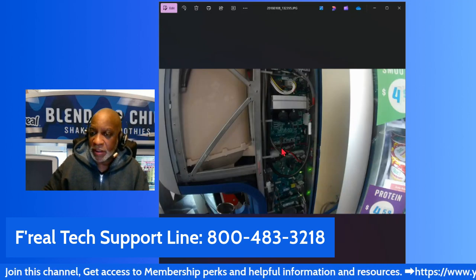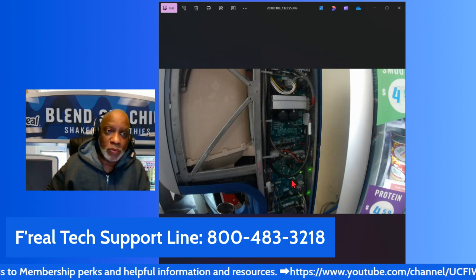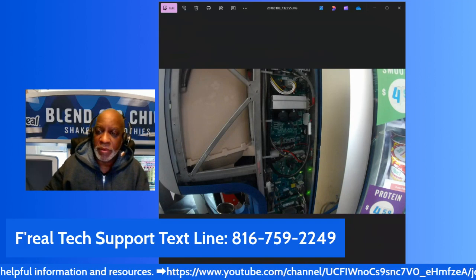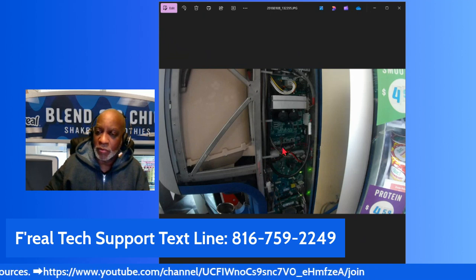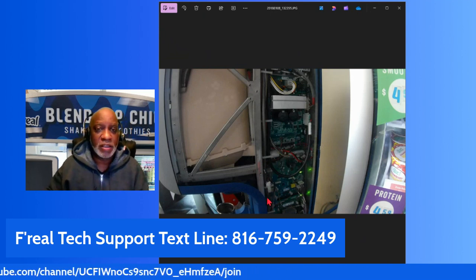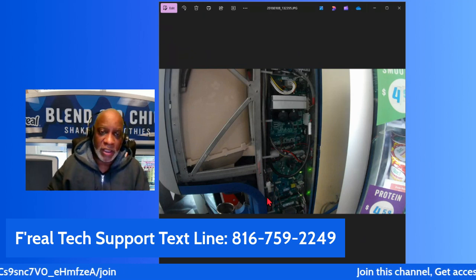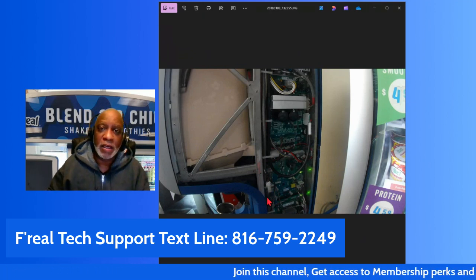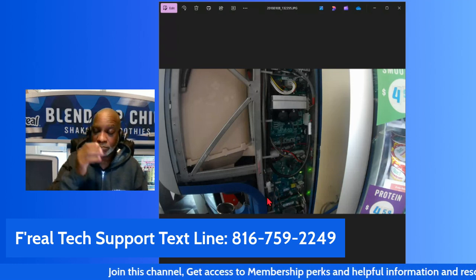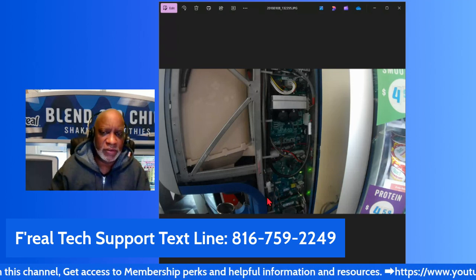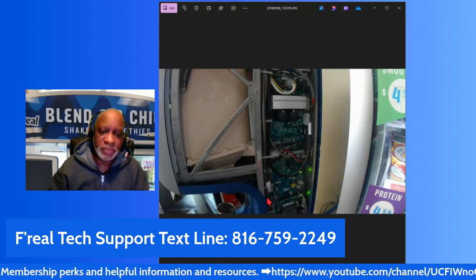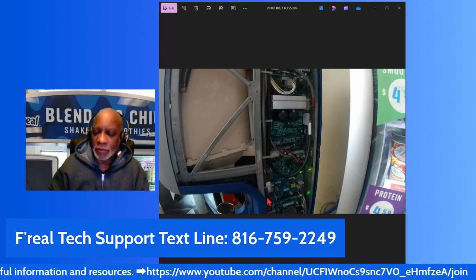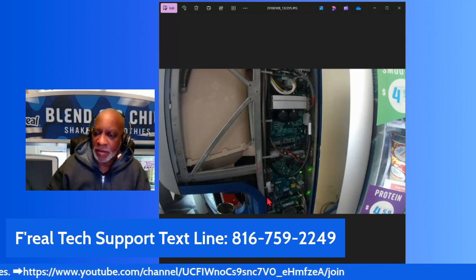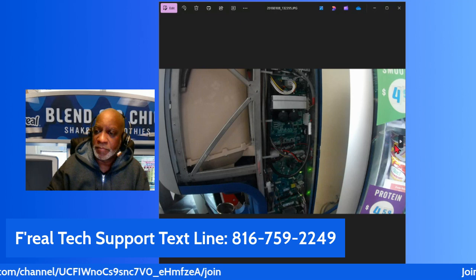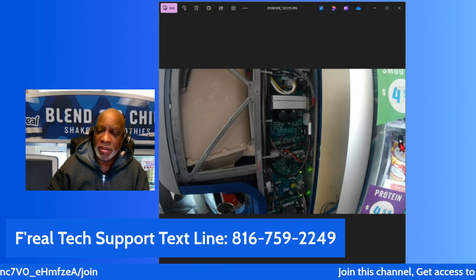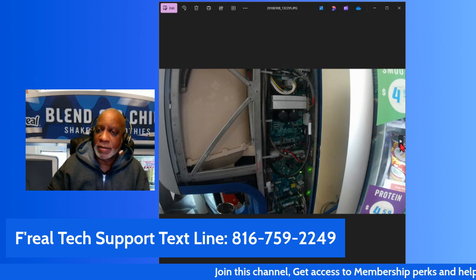And then right here, I have everything back in place. I have the unit back up and running. It is operational now. I still have to let it go through an initialization cycle. It'll initialize and then it'll go into a deep clean. The deep clean is between 12 to 13 minutes, I believe. But it will go through that deep clean, and then it will be ready to go so that you can do a sample blend to test it out, a test blend.